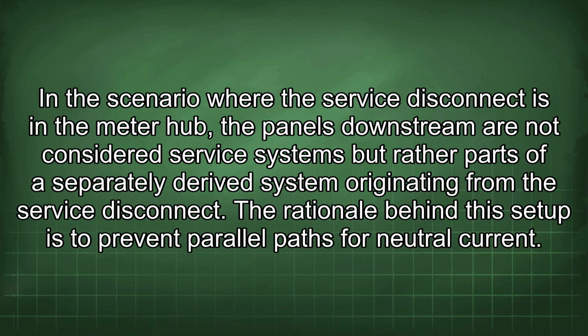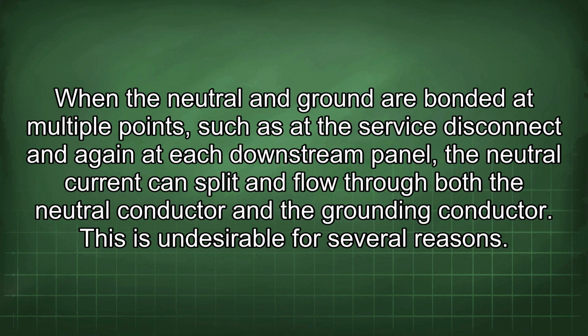In the scenario where the service disconnect is in the meter hub, the panels downstream are not considered service systems but rather parts of a separately derived system originating from the service disconnect. The rationale behind this setup is to prevent parallel paths for neutral current. When the neutral and ground are bonded at multiple points, such as at the service disconnect and again at each downstream panel, the neutral current can split and flow through both the neutral conductor and the grounding conductor. This is undesirable for several reasons.